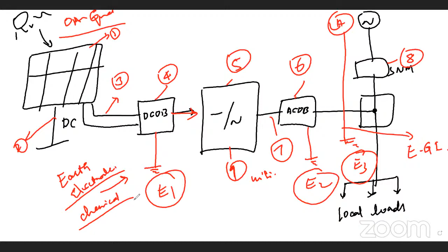Definitely, the lightning arrestor has to be connected through an earth flat only, a GI flat only. But for the DC and AC earthing, depending on the capacity of the system, you can use a 10 square mm cable or a 16 square mm cable to divert the fault current to the earth. So you must use the proper earth electrode to discharge the surge or the fault current, with chemical bonding. Chemical bonding is a must for solar applications. So these are the key components from the block diagram point of view.